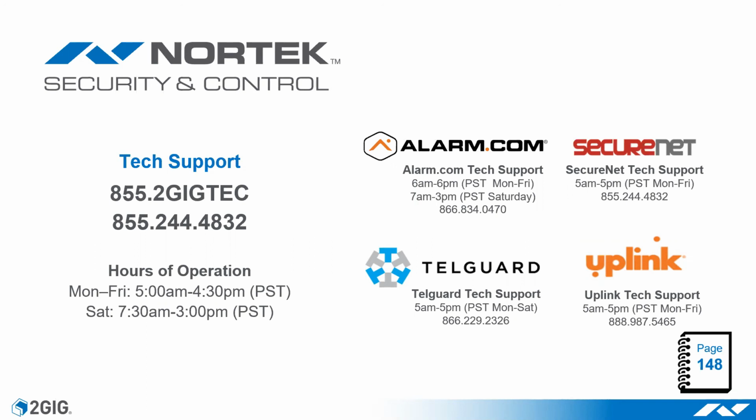So I do recommend calling our tech support again. And if they're not able to help, you can get a hold of your sales rep, and they'll get a hold of us in the training department, and we can work with you directly to figure out what's going on with that product. But it might be not enough amperage to power those sirens. We can then figure out how to get you a correct solution to get your siren up and running, which may be an external power supply for your sirens in particular.